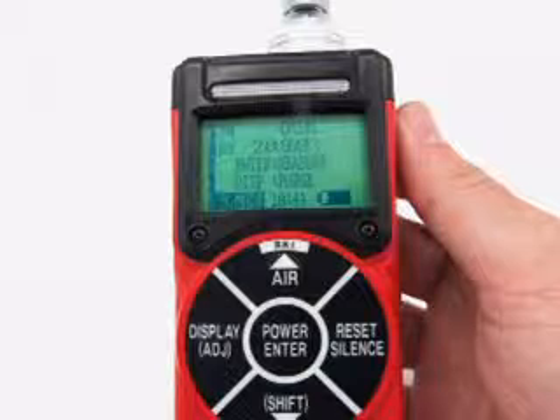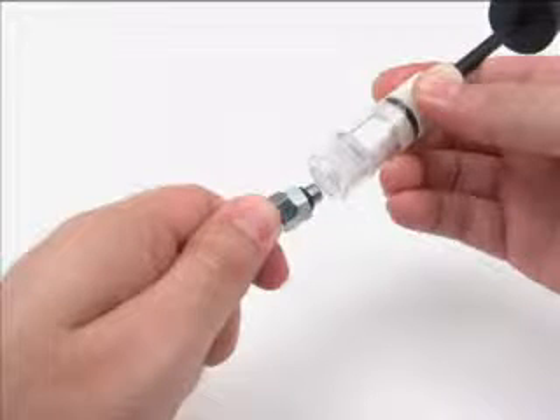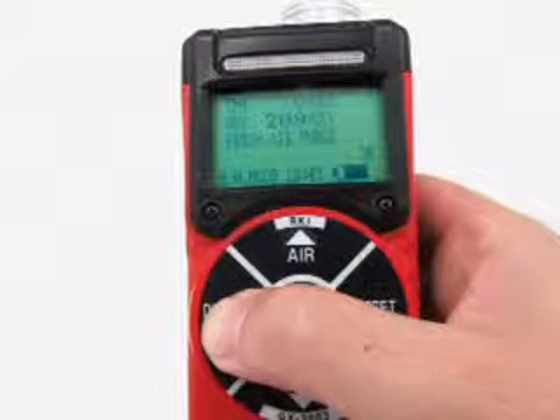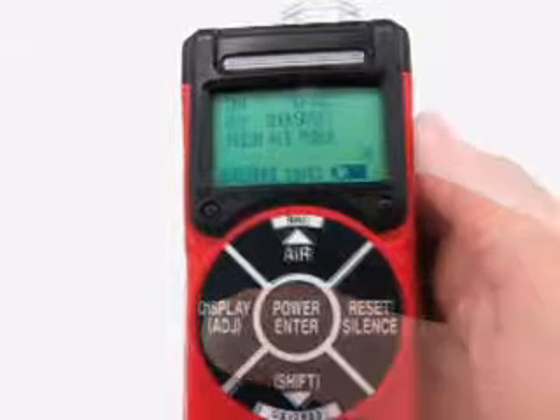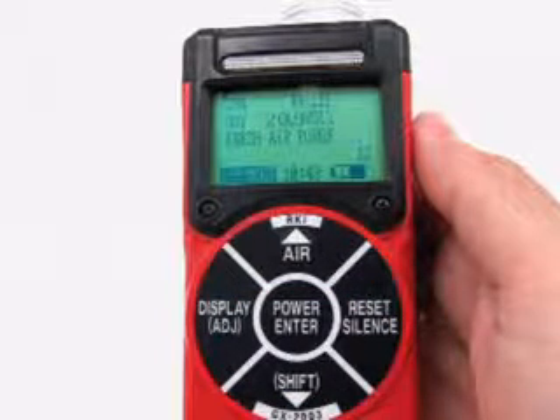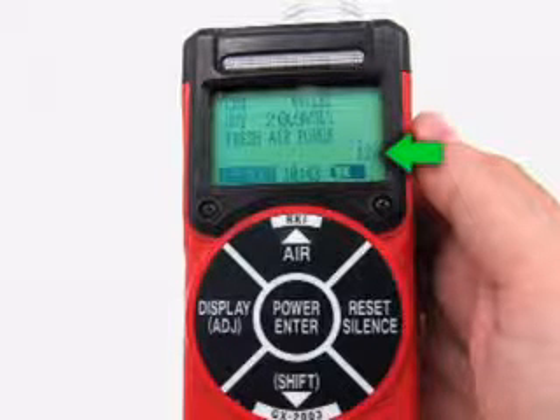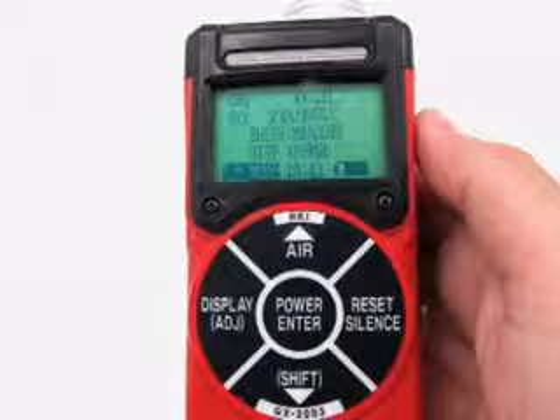If a high concentration of methane was encountered, a fresh air purge can be performed to purge the hose, probe, and GX2003 of gas before the next bar hole test. To perform a purge, remove the probe from the bar hole so that the instrument will draw fresh air. Press and release the display adjust button. The display will now indicate fresh air purge below the oxygen reading, and the purge time will begin counting down from 30 seconds in the lower right corner of the display above the battery icon. When purge is complete, the screen will return to the initial bar hole mode screen.